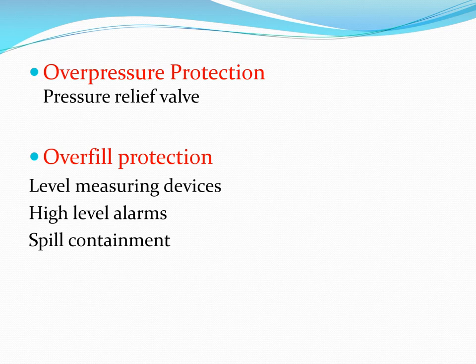Overpressure protection requires all vessels to have pressure relief devices, especially pressure relief valves, which must be provided to all vessels storing material subject to pressure buildup. The relief devices can be located directly on the vessel or installed within a process or utility pipeline connected to the vessel.